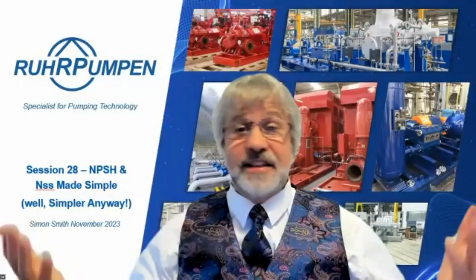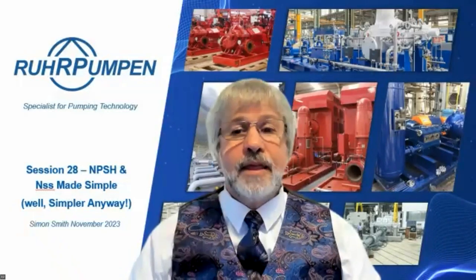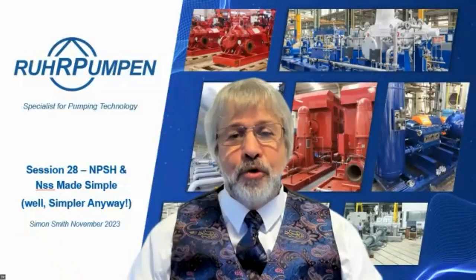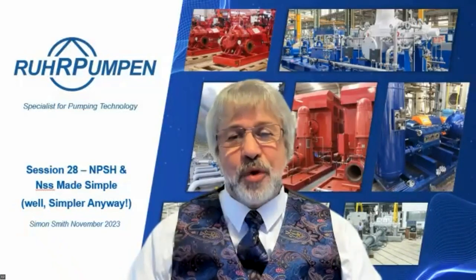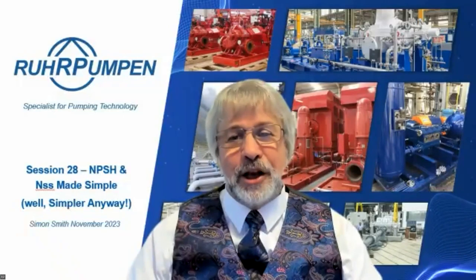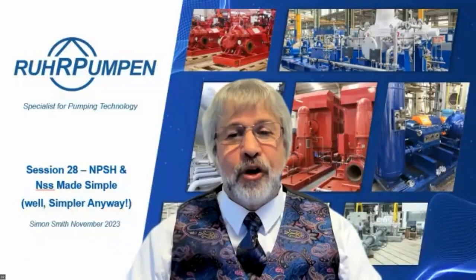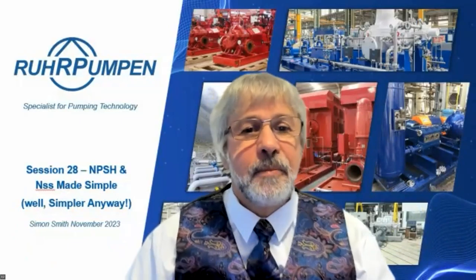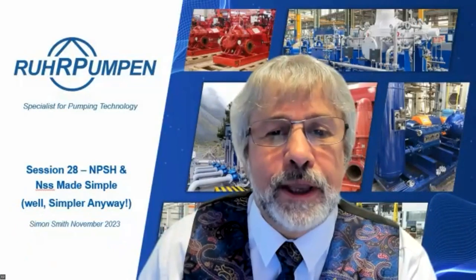Hassan Khan asks: would you recommend NPSH prediction using CFD simulation during design stages? Yes, that's exactly what we do - and many other techniques as well. This is how we've been able to move forward from the 1950s-1980s, when the only way to get a low NPSH pump was to make a large eye pump.